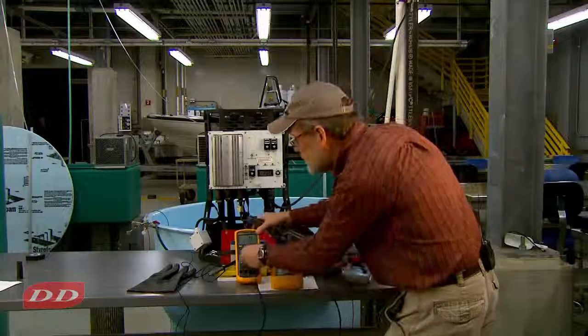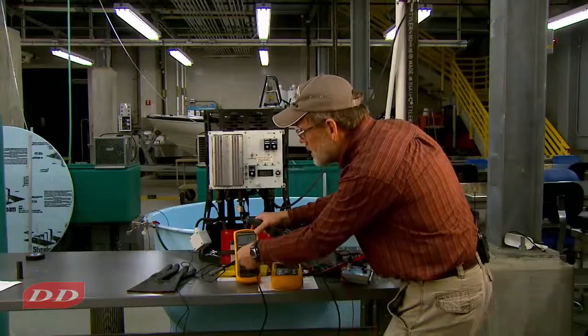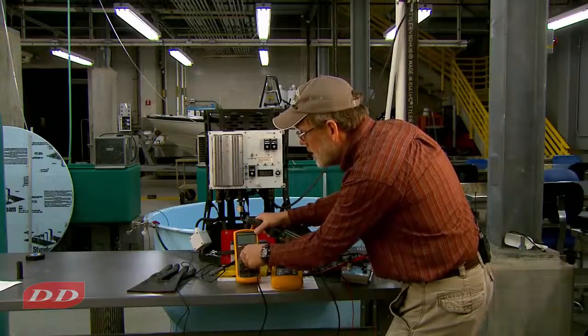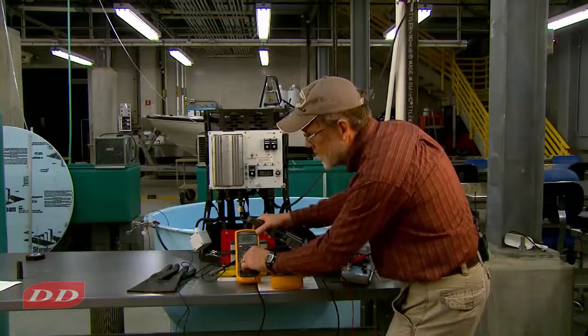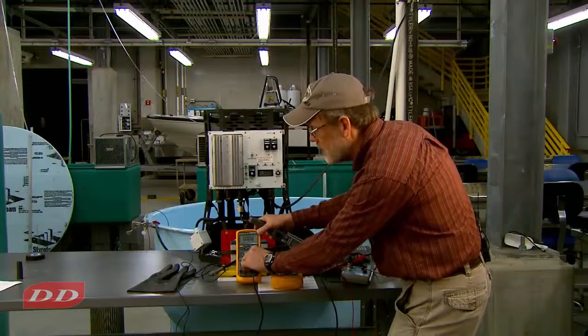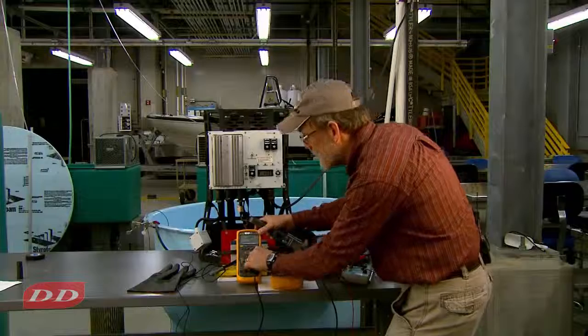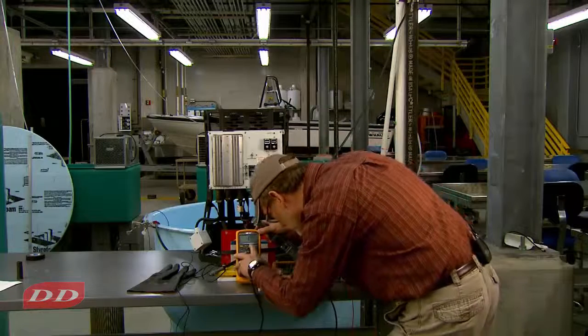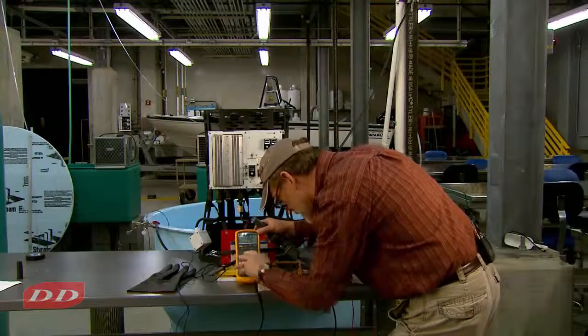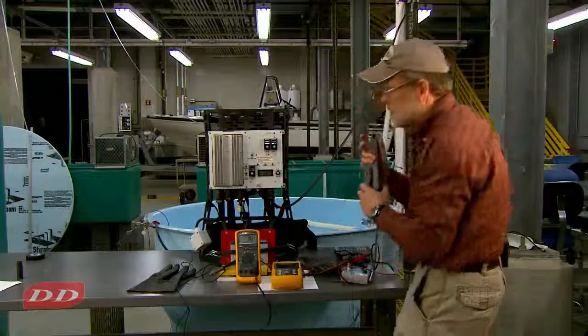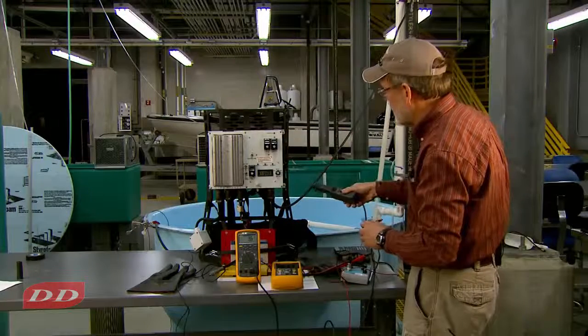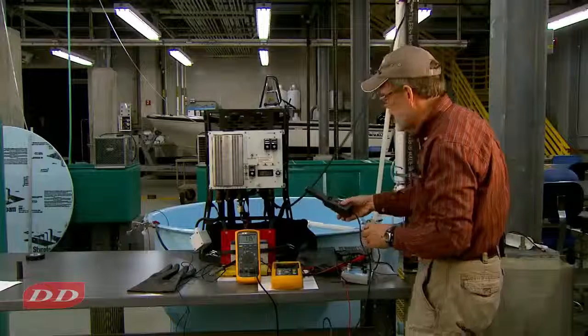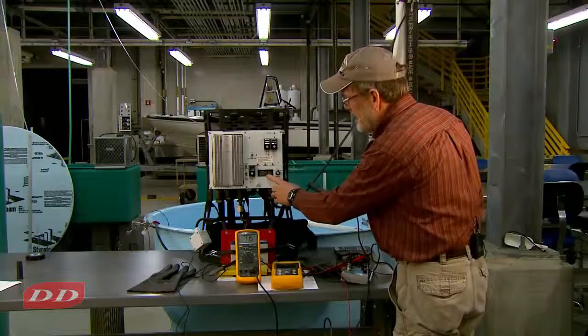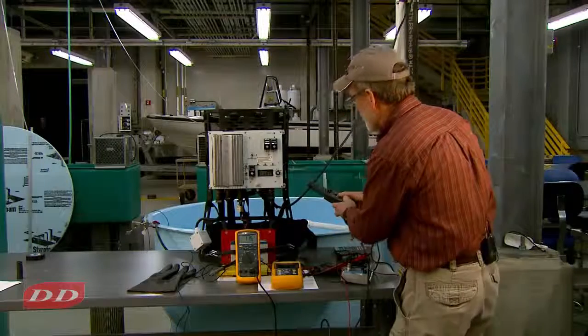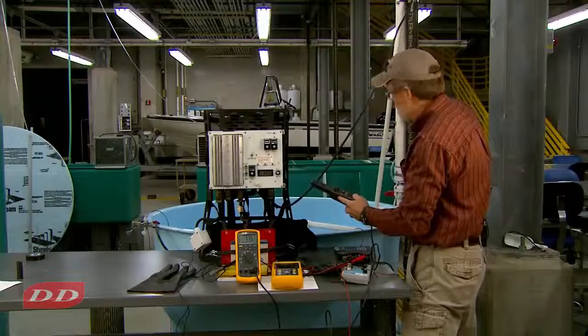So again, I'll set this unit to DC volts, but actually I'll set it to millivolts because this is going to be a millivolt scale. I want to make sure that we get peak and make the clamp on. We'll compare the ammeter reading with this reading. So here we go, fire in the hole.